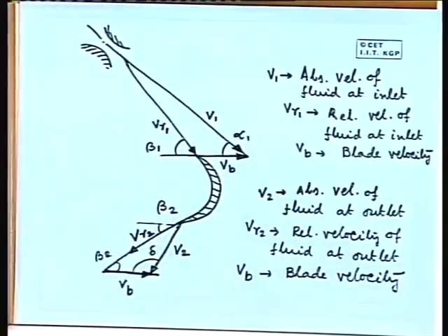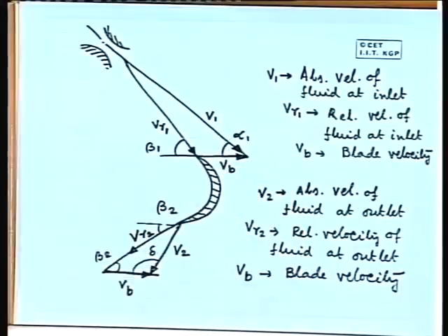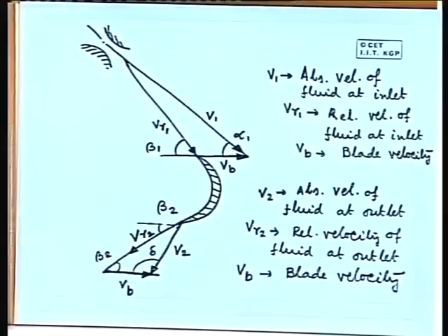So, steam will pass through the nozzle. When it comes out of the nozzle, it will come out as a high velocity jet. That is what we have discussed so far. That is the sole purpose of using the nozzle. And then this high velocity jet will impinge on the blade. Okay. So, when it is impinging on a blade, it will move over the blade passage and there is a change of momentum. So, the fluid momentum will be transmitted to the blade passage, or some amount of force will be exerted on the blade passage and the blade will move. Then another blade will come and get the supply of steam, again that will move, a third one will come. So, this continuous rotation will go on, and ultimately from the blade the motion will be transmitted to the disc and shaft, and from the shaft we will get the output. So, that is how it works.